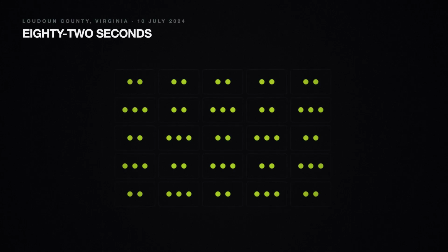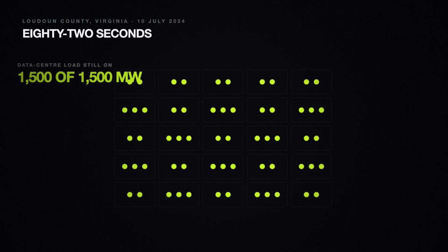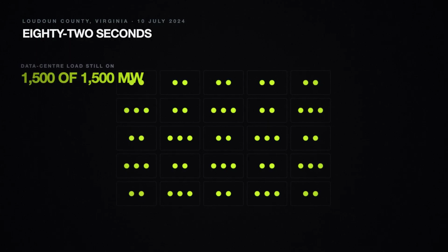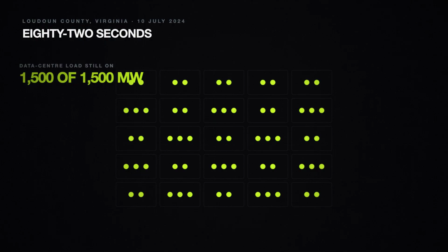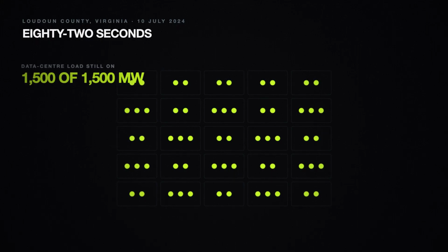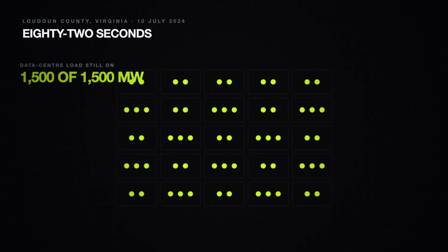On the evening of July 10th, 2024, a piece of equipment about the size of a fire hydrant failed on a 230 kilovolt line in Northern Virginia. It was a lightning arrestor. Its job is to catch a surge and send it safely to ground. When one fails, it becomes the fault it was installed to prevent. The protection system did exactly what it was built to do.